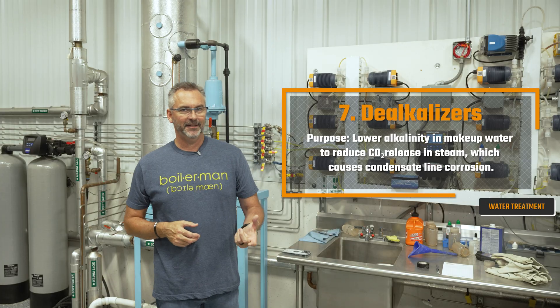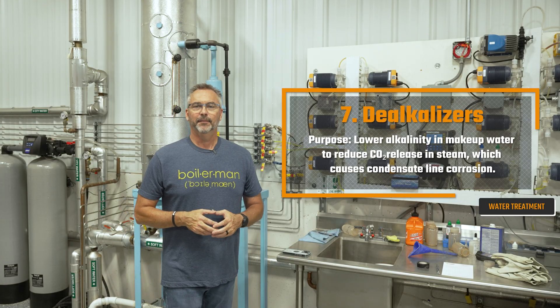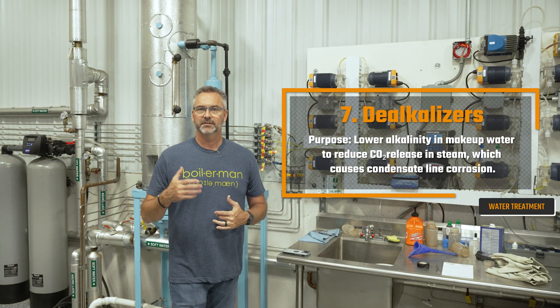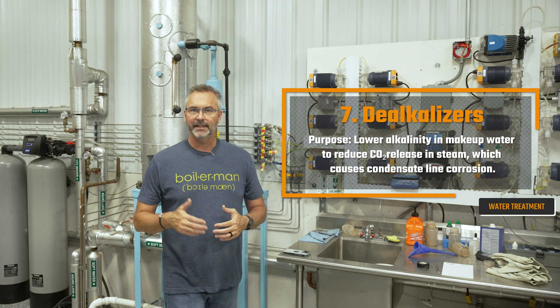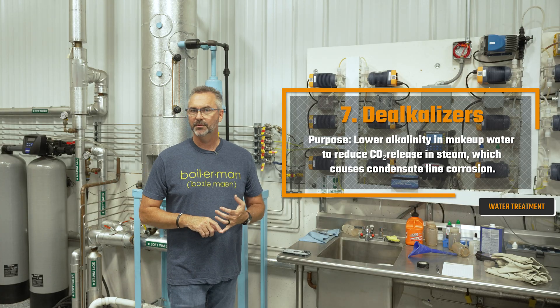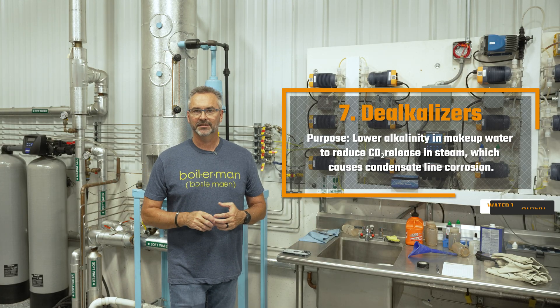Number seven is dealkalizers — acid neutralizers. Their purpose is to lower alkalinity in makeup water to reduce CO2 release in steam, which causes condensate line corrosion.